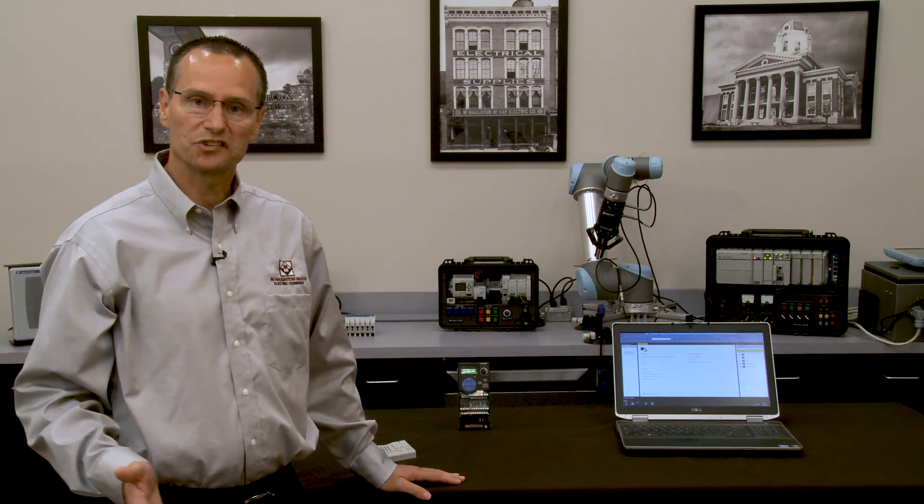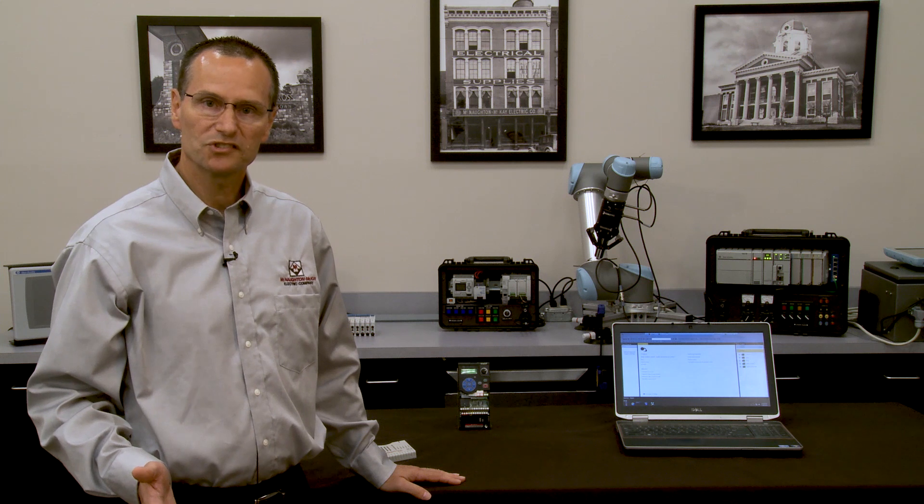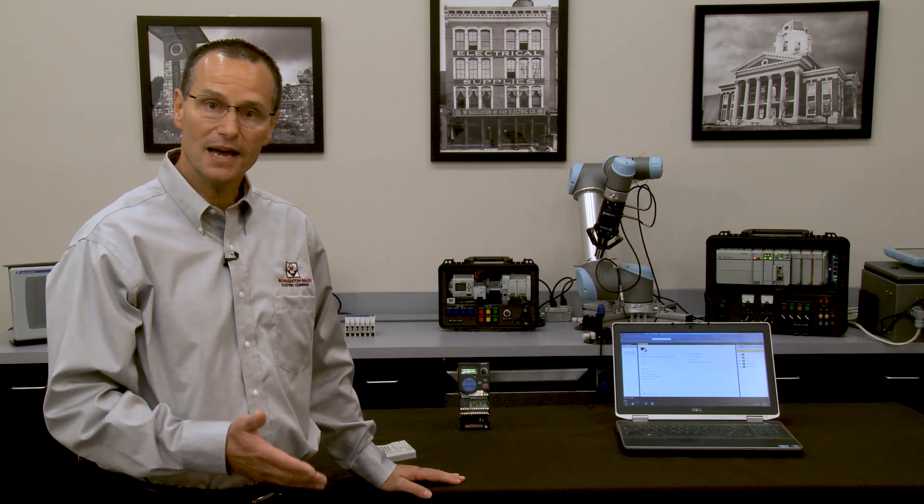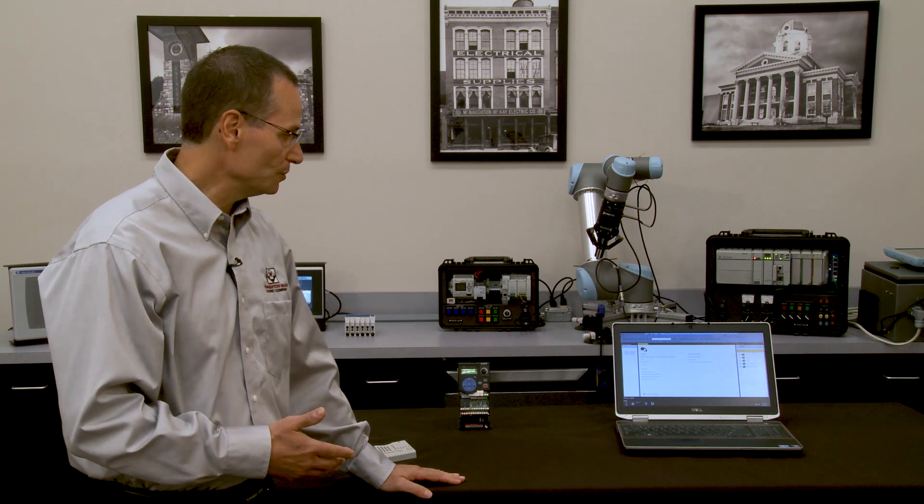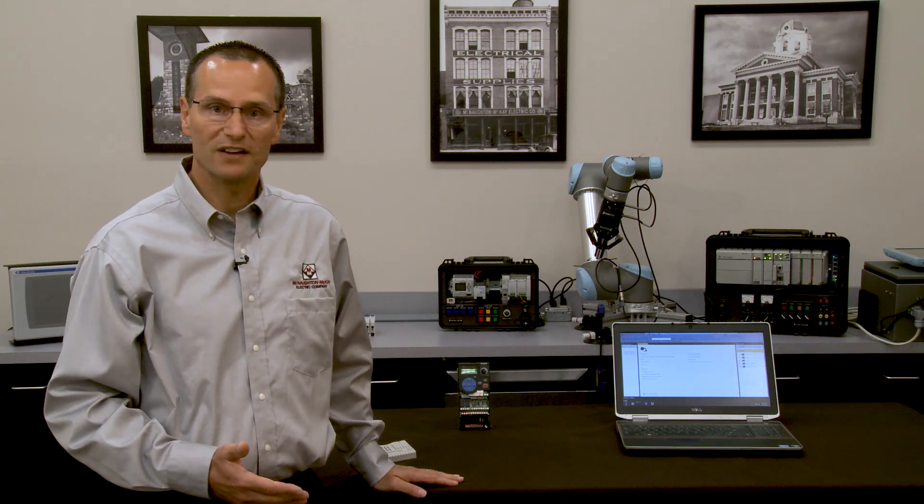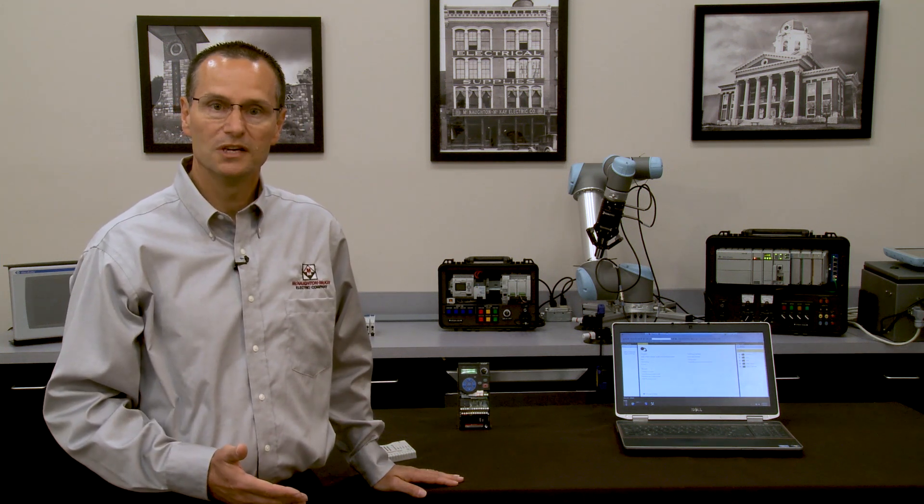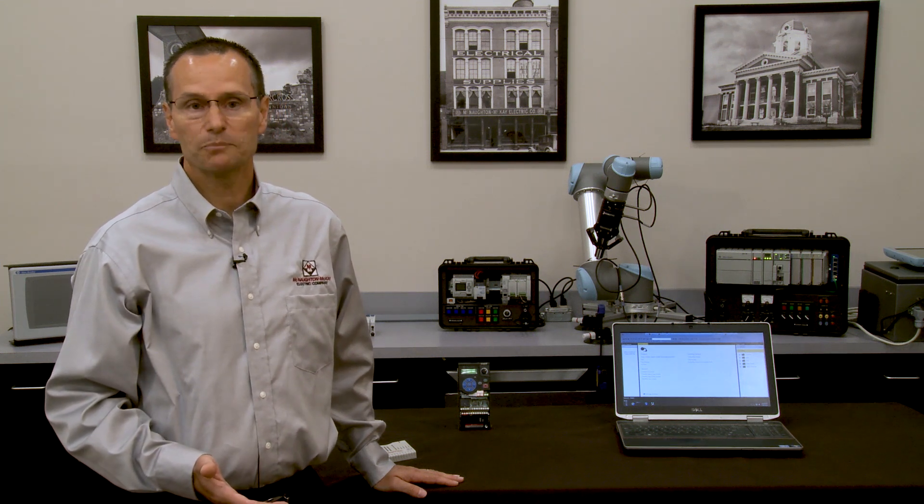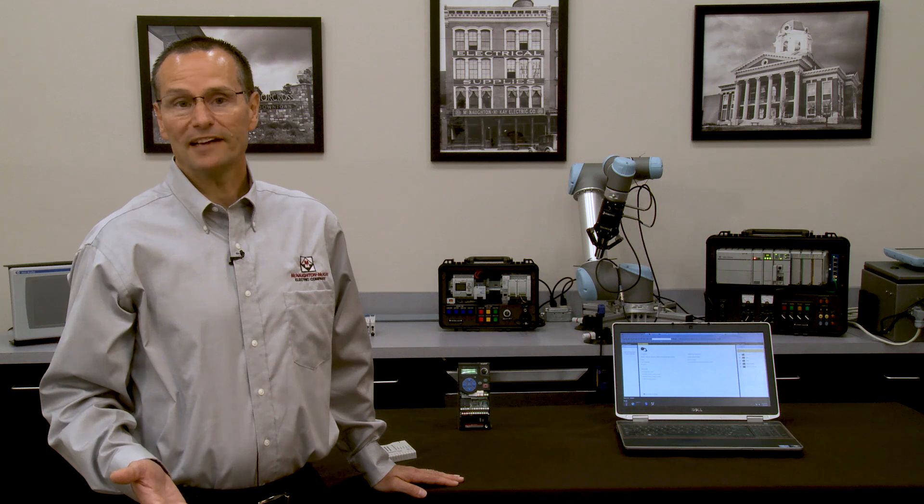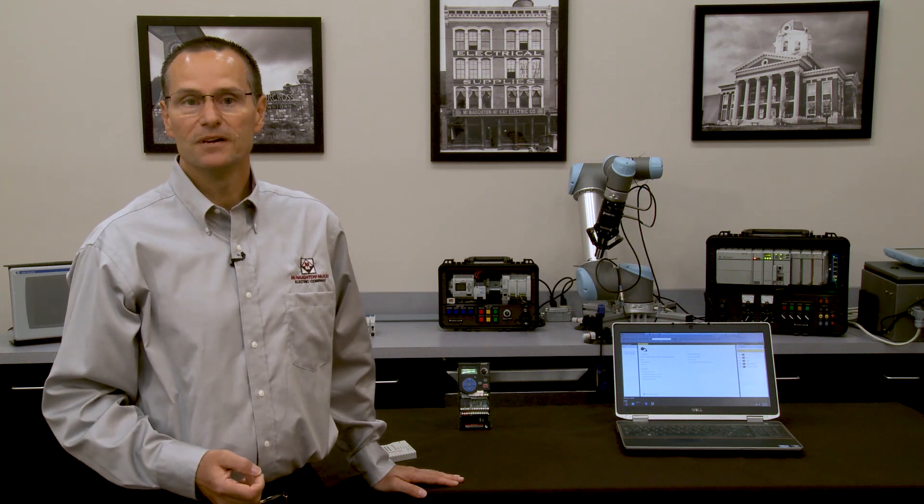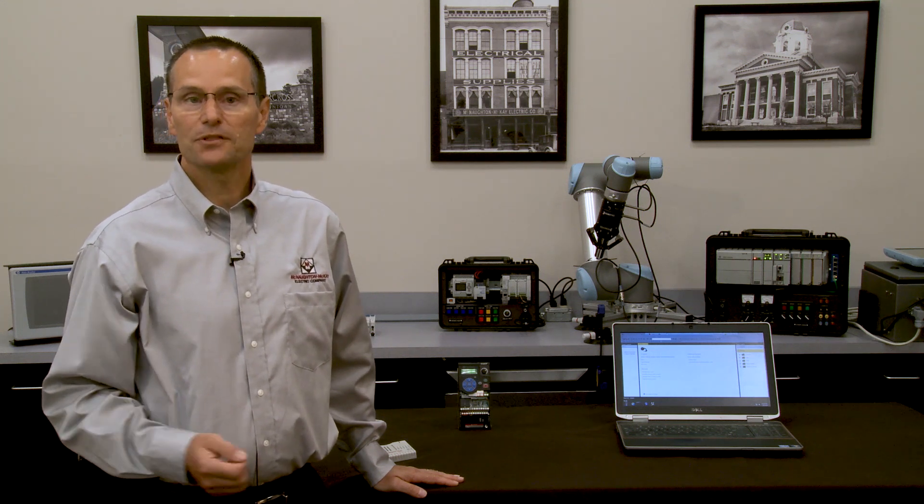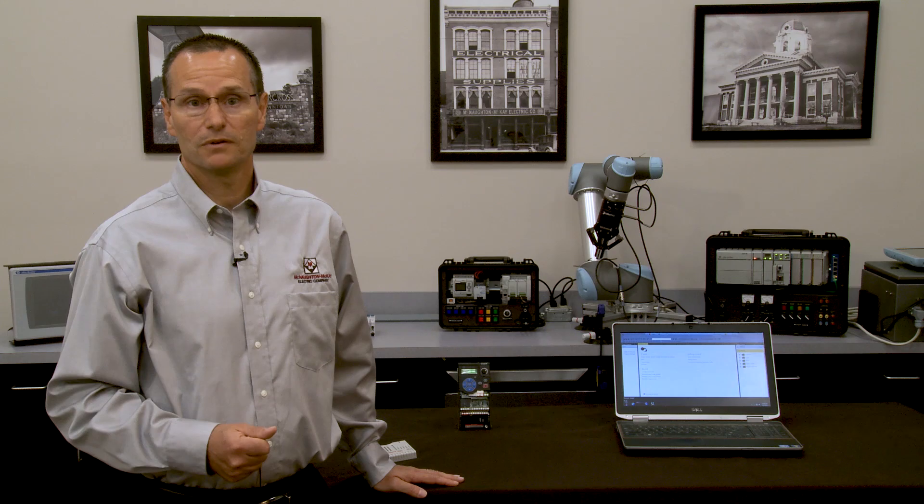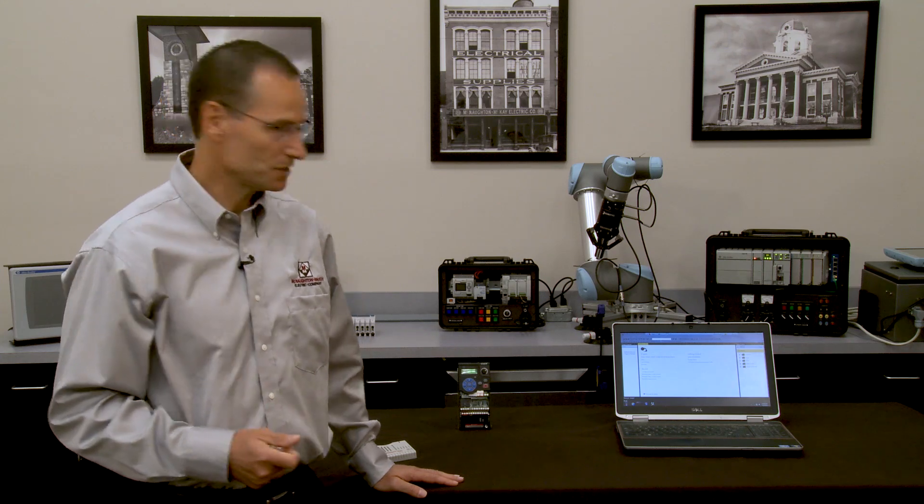Commonly, with Compact Logix or Control Logix processors, you can utilize Ethernet IP and connect to the ACD file of the PLC to upload and download and store all your drives parameters. But there are times when you don't have a PLC connected or perhaps you just want to access the drive because there's not an Ethernet port available on your Ethernet switch.